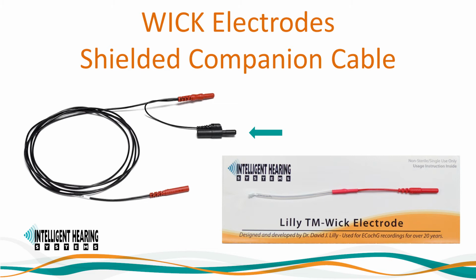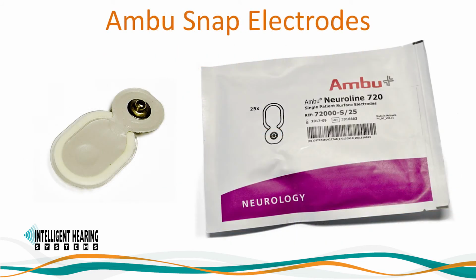The shielded ground extension reduces noise contamination of responses and provides for enhanced signal-to-noise ratios. When using snap leads, IHS recommends the use of AMBU neurology electrodes specifically designed for the type of evoked potentials we're acquiring. The AMBUs must be conductive and not expired. When storing a package of disposable snap electrodes, they must be sealed tightly in a Ziploc bag in order to prevent them from being exposed to the elements and drying out and losing their conductivity and function.